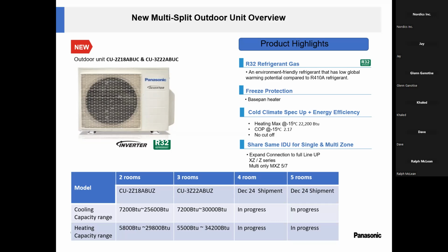Okay. And for heating capacity, we got pretty good numbers there. 5,800 being minimum, all the way to 29,800. 5,500 as being minimum, to 34,200 in the 3-zone. We will update you when we get the 4-zone and the 5-zone. The beauty about this multi-zone is you can use the Nano X unit and the non-Nano X unit. They are interchangeable. You can mix and match whichever way you want to go. So please keep that in mind, okay?